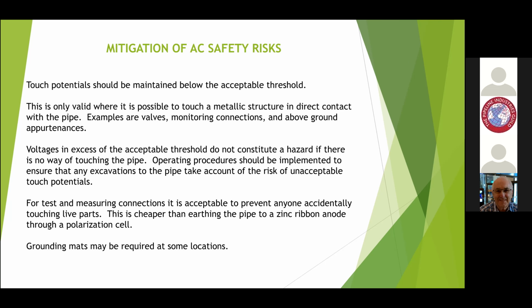It's obviously a somewhat bigger risk for longer animals such as horses and cattle. In such cases, what you have to do is make the gradient flat - in other words, take away the hill. We do that by putting a grounding mat at the location where that happens, and sometimes you'll see these installed at valves where they can't effectively isolate it any other way. They equalize the potential around the structure so that both legs are at the same potential, at the same level.